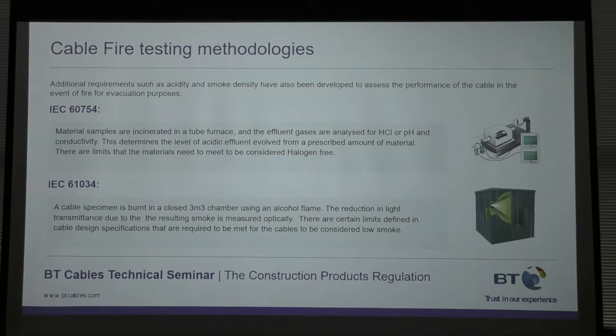IEC 61034 is a smoke test, a 3 metre cubed chamber, where basically you burn a sample of cable under a clean alcohol flame. There's a light receiver at one end and a light source at the other end, and the cable's burnt to see how much impact it has on the incident light. So you're looking for at least 60% of the original light source being able to be received by the receiver.